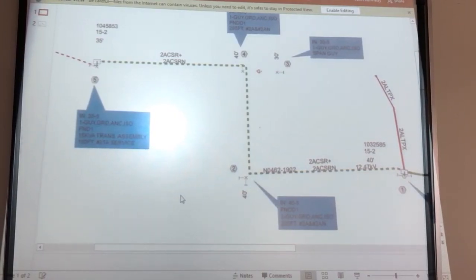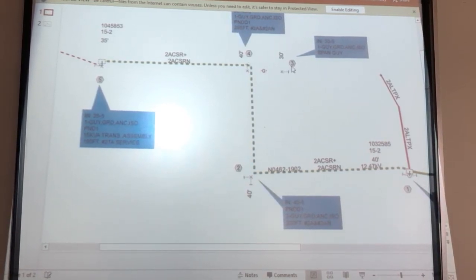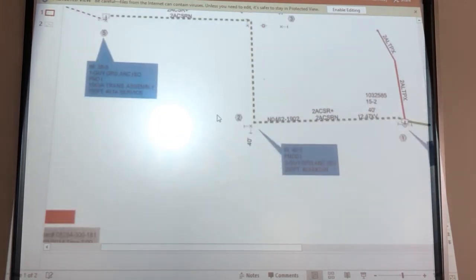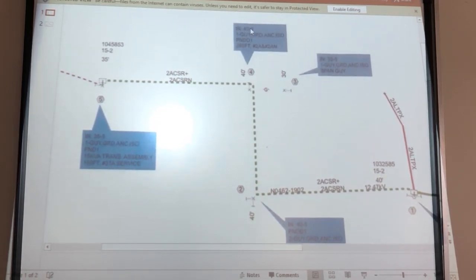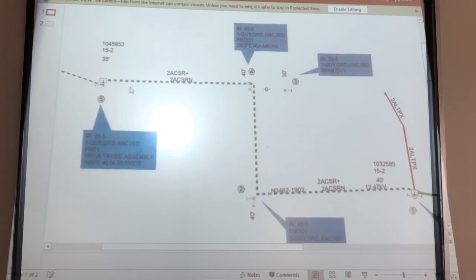So again, I want to recap, going back to location 4 and location 3. The installations here, again, install a 40-foot pole, class 5, 1 down guy assembly, double dead end wire in each direction. The amount of wire that's in this span of wire going back to this dead end pole to location 5.